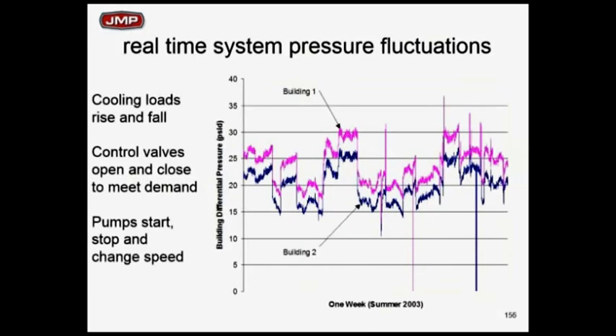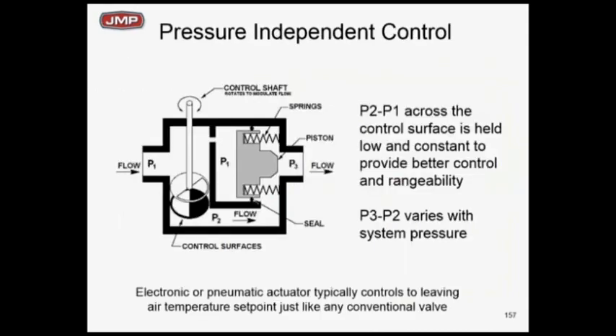Here's some charts. I gave you one on building one. Here's another building. And you see that it's varying 10 to 15 pounds easily, very quickly across the valves. What does that mean to you? If you have a two-way valve and you vary the differential pressure across it, the load's not changing instantly, but the flow is. And we'll show you a chart of that in just a few minutes.